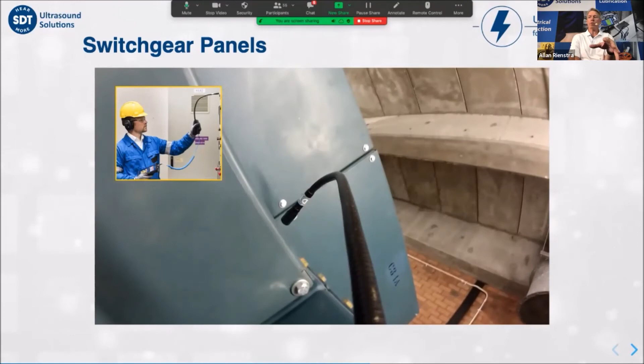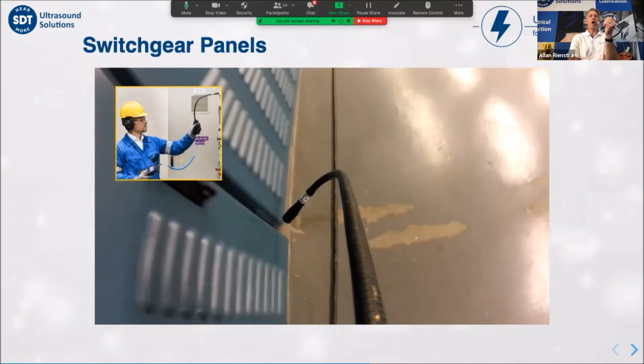But imagine you could pick up an ultrasound gun or device as our inspector is doing here, and check anywhere there's an air gap around the door, a vent - these panels are not hermetically sealed. Any air gap is an opportunity for ultrasound to go from inside to outside. It will travel through the steel, but remember, it's introverted - it wants to stay in the cabinet and just chill. But we can hear it through those gaps in the seals.